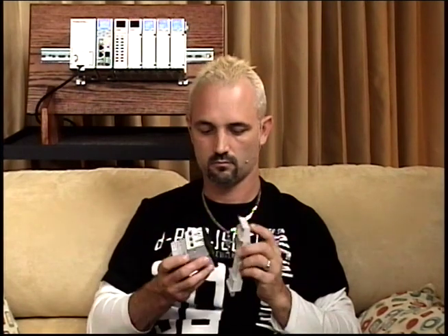We also sell auxiliary contacts. And again, we have the situation with the base plate that Shane's holding. We can put the manual motor protector on that base plate, add a contactor to it, and our overload relay is actually built into the manual starter. So with the contactor, we end up with the short circuit protection, the overload protection, and the contactor, so we end up with a combination motor starter. Okay, cool. Yeah, I think I threw another little schematic in here showing a reverse.